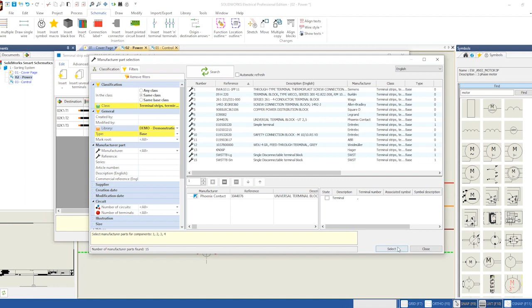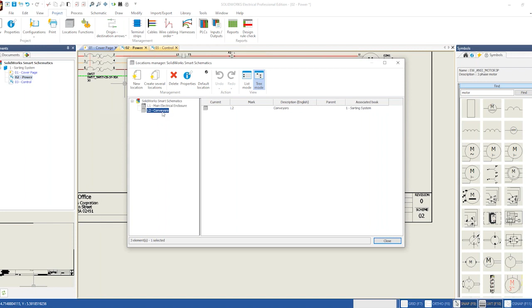Now typically going to our motor we'll use a cable. One thing I want to point out is that we have location capabilities inside our project - we can define those ahead of time. I've got 2 locations: the electrical enclosure, and then a conveyors location, which is L2. My motor technically is going to be out on my L2, not on my electrical enclosure.